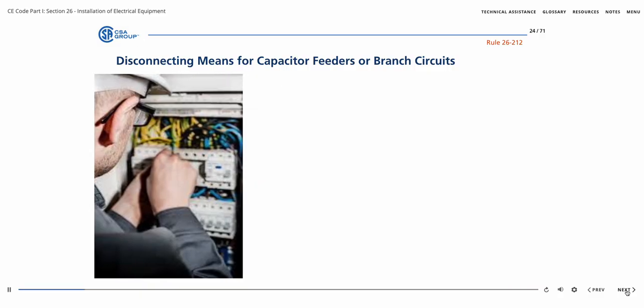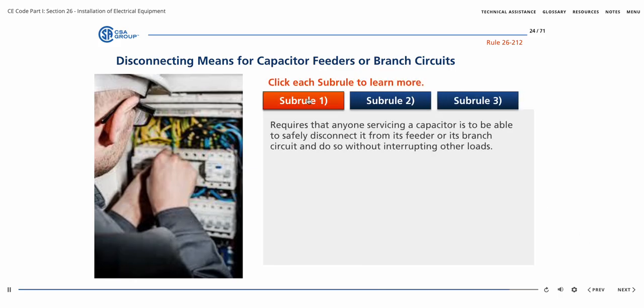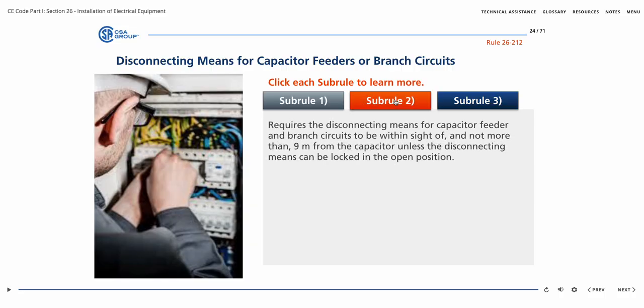It is very important that disconnecting of capacitor feeders or branch circuits be carried out very carefully. Rule 26-212 ensures this safety by enforcing the following requirements. Sub-Rule 1 requires that anyone servicing a capacitor is to be able to safely disconnect it from its feeder or its branch circuit and do so without interrupting other loads. Sub-Rule 2 requires that disconnecting means for capacitor feeder and branch circuits are to be within sight of and not more than 9 meters from the capacitor, unless the disconnecting means can be locked in the open position.